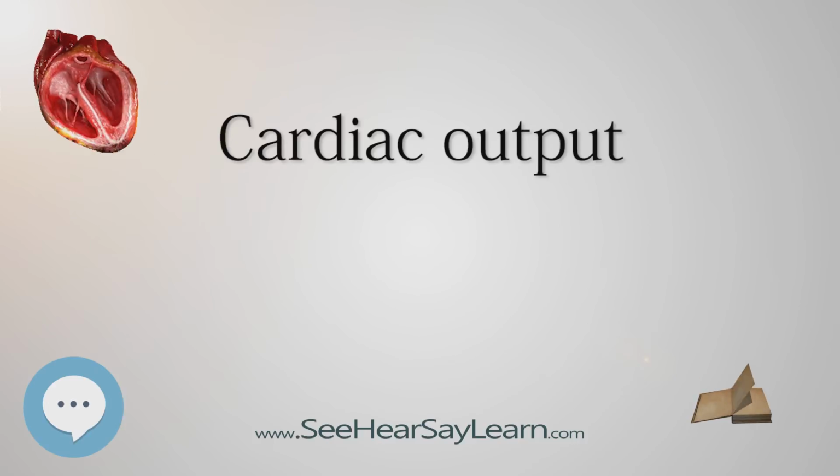This correction worked under all of the circumstances it was tested in, even when it was not designed for it, because it applied general physiological principles. This innovative brachial pressure waveform reconstruction method was first implemented in the Finometer, the successor of Finapres that TNO introduced to the market in 2000.